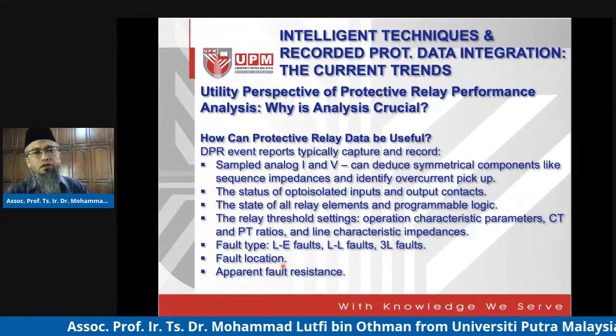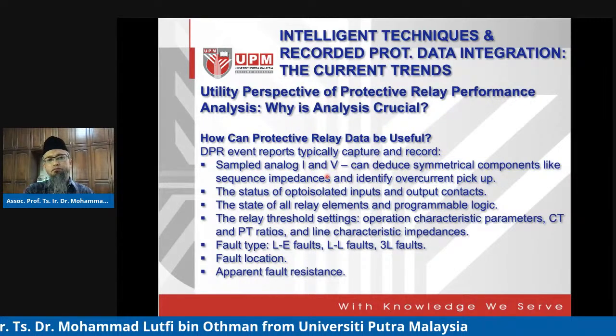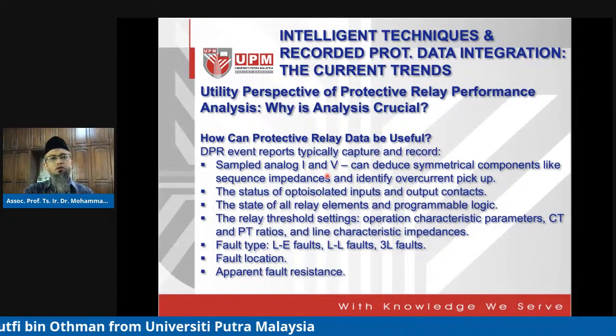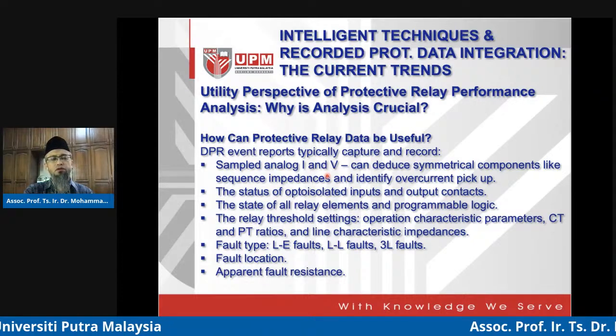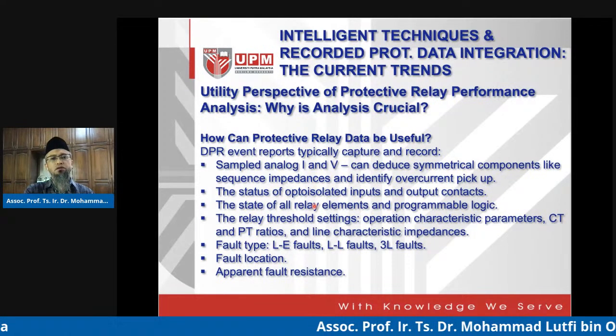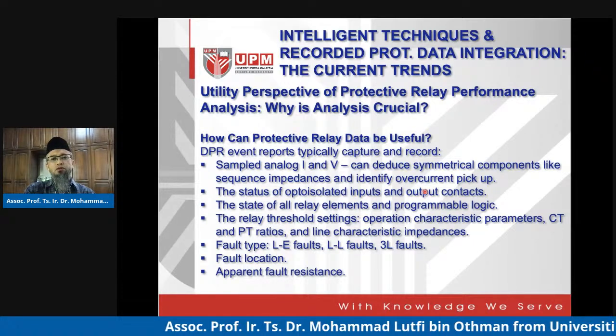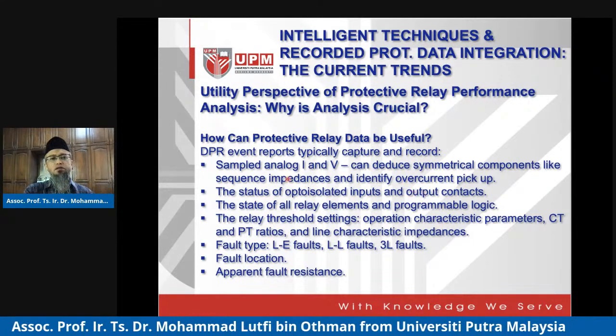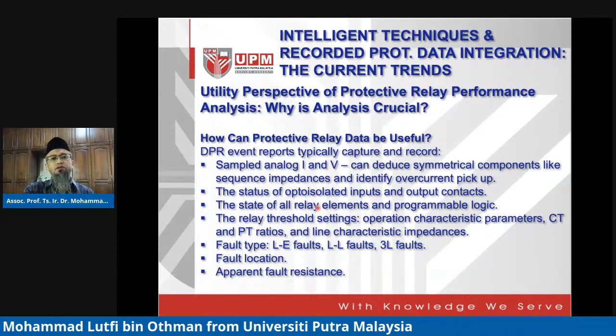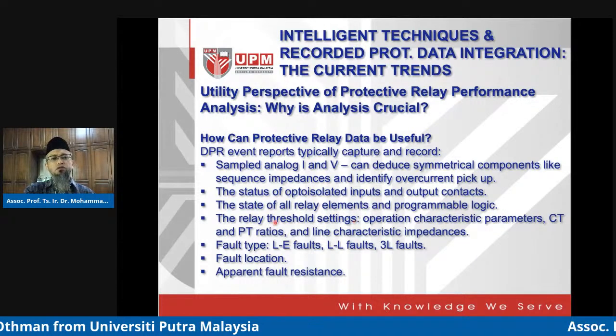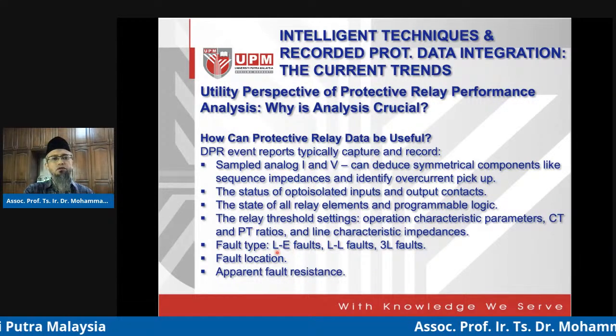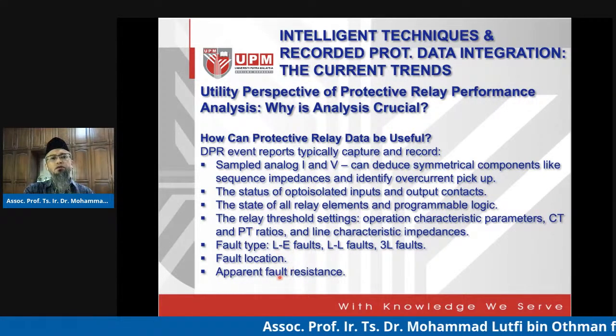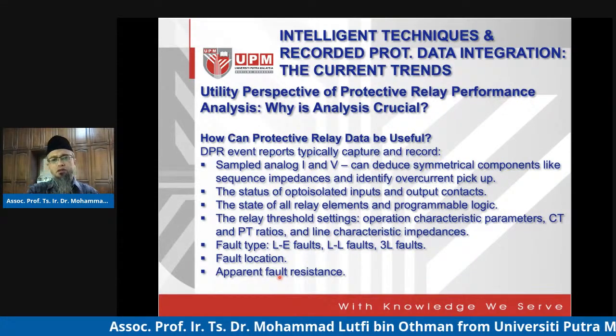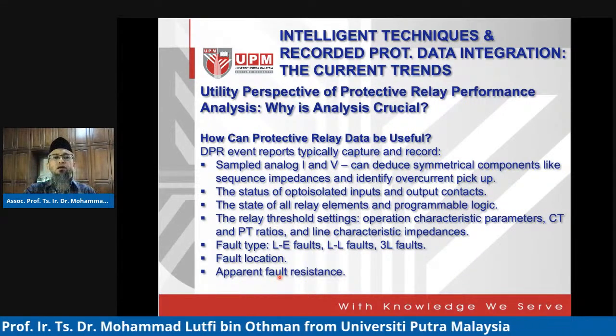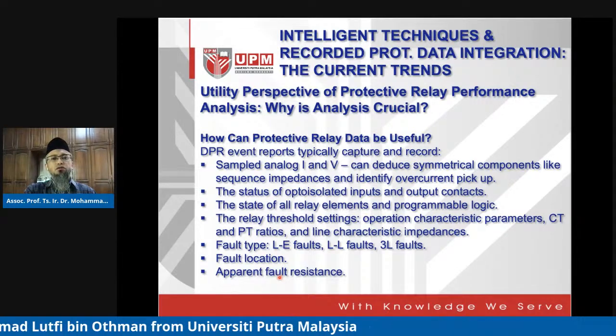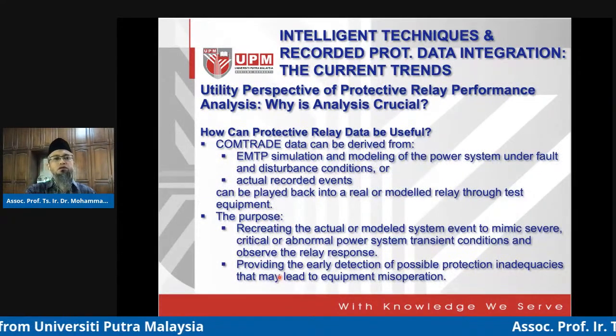How can a protective relay data be useful? There are all sorts of values, parameters, and quantities we can extract from the report: the voltages, the currents, the inputs, output contacts, or even those of other devices like circuit breakers. The various functional elements within the relay, the current transformer, potential transformer, the type of faults, location of faults, even the apparent fault resistance, or fault impedance, can also be known to engineers who want to make full use of the data. That's why the data is very important.